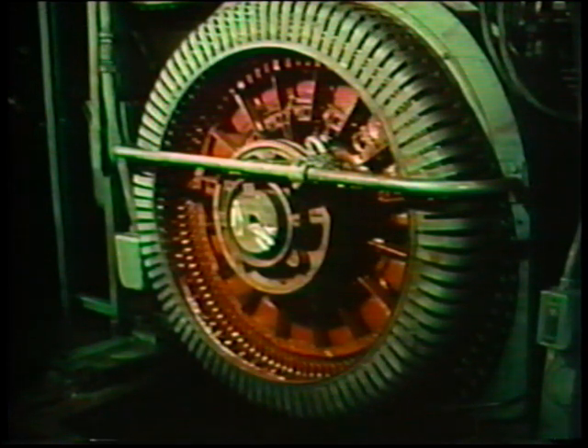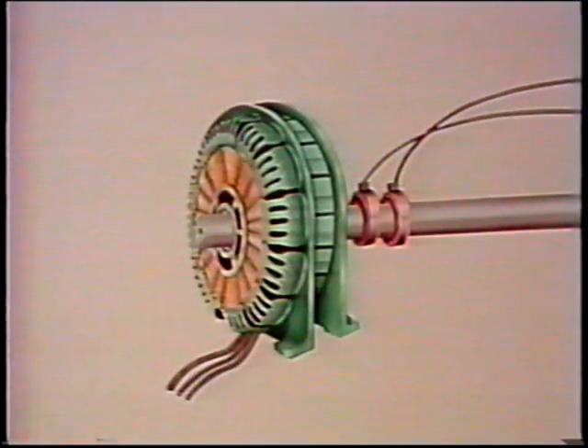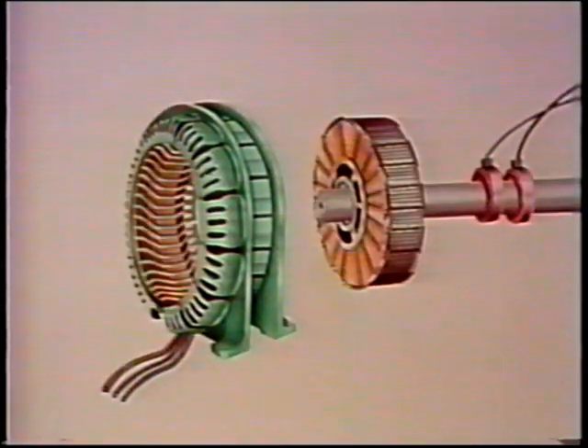at low speed. Like all motors, synchronous motors have two main parts: a stator and a rotor. Basically, synchronous motors operate by using three-phase alternating current in their stators to produce a rotating magnetic field. The rotor of a synchronous motor has electromagnets that lock in with the stator's field, so that the rotor turns at the same speed as the stator's rotating field.